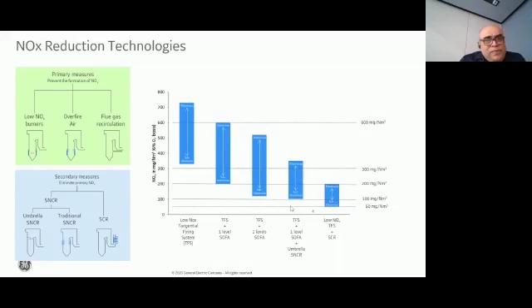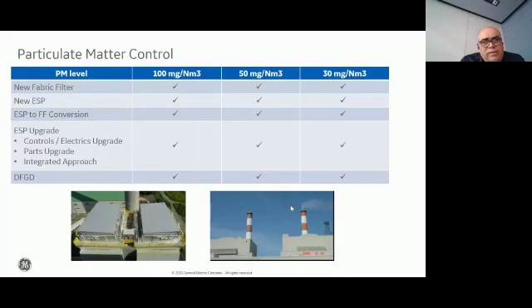When it comes to particulate emissions, if you are having emissions suitable for 100 milligrams, then we have a gamut of solutions. Typically, you can have a fabric filter or a new ESP or an ESP to fabric filter conversion, or you can go in for upgrades of the ESP controls or parts to reach the emission requirement you are looking for in that particular project. And even if you go in for dry FGD or semi-dry FGD solutions with a fabric filter, then you will be able to meet the particulate matter control.